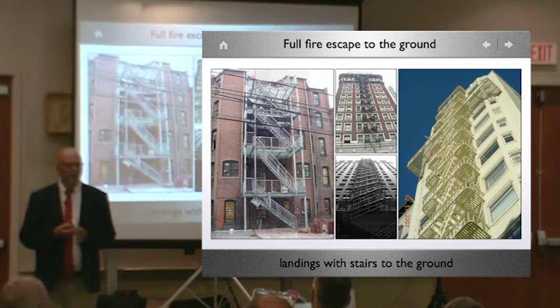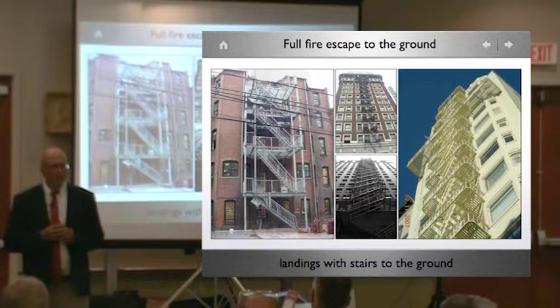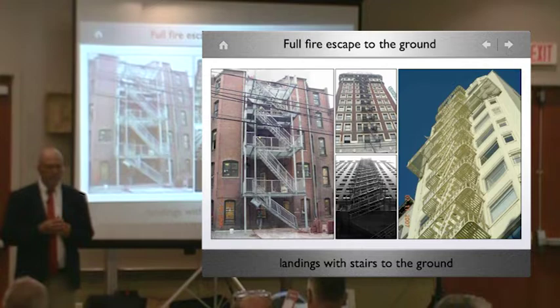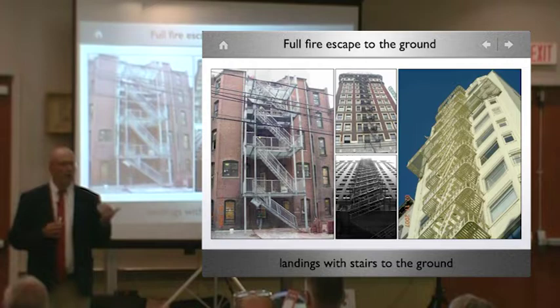And for me, because it's an existing aluminum one, there's only three things that can happen. Okay? You can certify it, not accept it, or you can fail certification, and you're putting in a second egress. Or if it's a legal conforming existing fire escape, then you can make repairs on it. But if it's legal non-conforming, no repairs of any type. You're actually non-conforming. Let's add windows should become doors. There's all these things that happen. So here's somebody that has dealt with this.